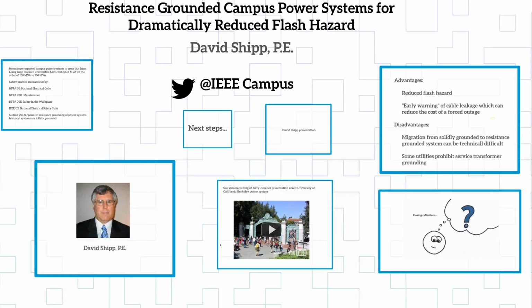I go to that master substation that feeds that hospital at 13.8, and instead of solidly grounding the Y connection at the utility transformer, or maybe you got a 20 MVA transformer that's 120 kV to 13.8 or so, I'll put a 400 amp grounding resistor, 200 amp, whatever the design allows us to do, and I change my protection. I need to make sure my lightning arresters that I have through the system can handle the different grounding system, and you can do that very economically. Now, if you've already got digital relays, it's just reprogram the relays using it for the industrial type of setting, and you don't even have to change the relays out. And so you can do it relatively inexpensively. You just got to make sure you don't miss all the points and stuff.